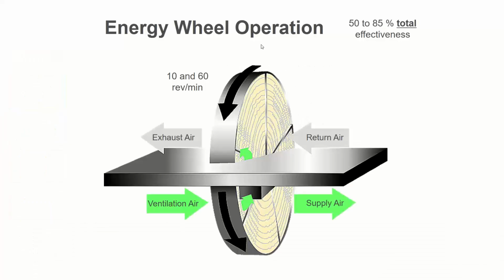All right, so this wheel on here, if I use it as my example, any air that leaks up this face of the wheel and accidentally goes back into the exhaust air is called the outdoor air correction factor. And you have to upsize the fan to account for that. So if you need 5,000 CFM, but 50 CFM is going to leak up the front and go out, I need to get a fan that's 5,050 CFM, so that I can get 5,000 actually going into the space.